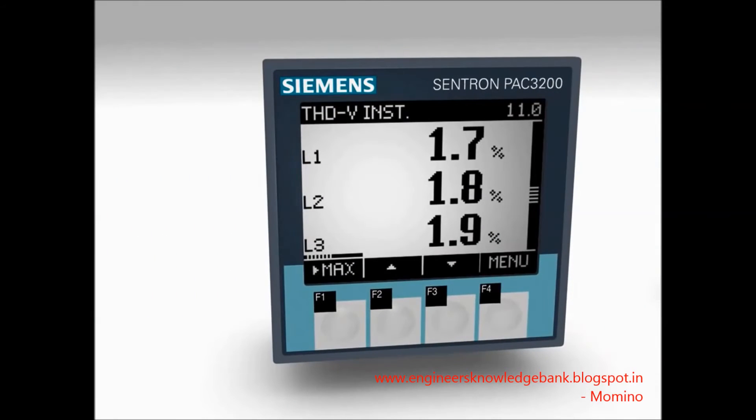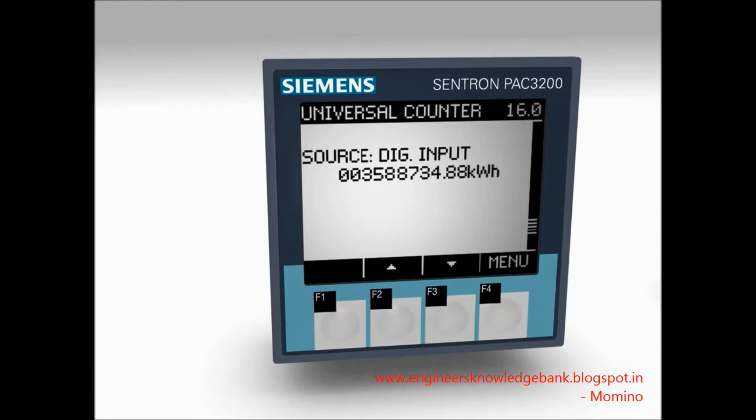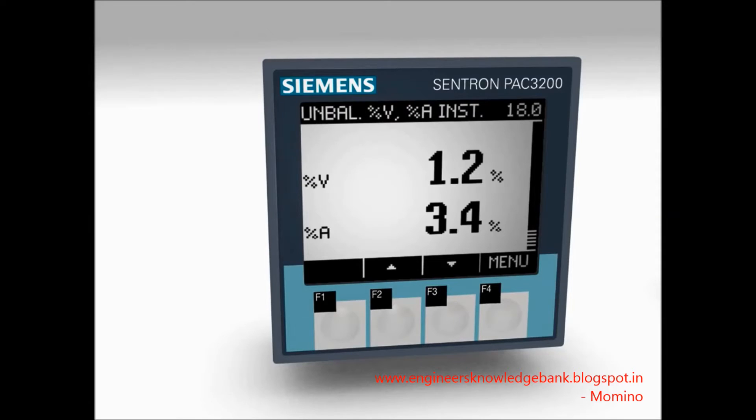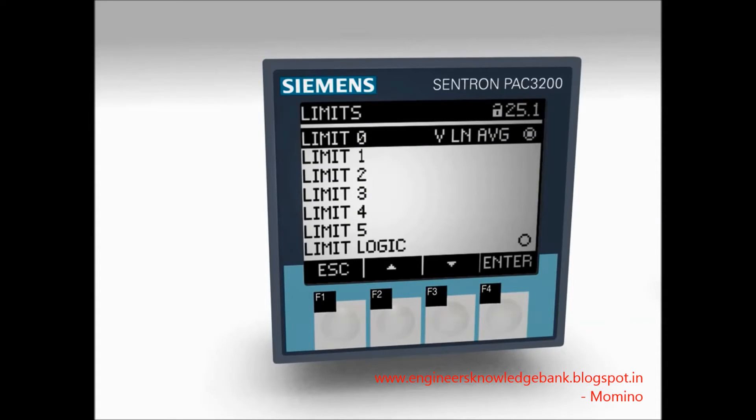The measuring device SENTRON PAC3200 provides more than 50 measurements and can be directly connected to a network up to 690 volts. Ten precise energy counters permanently log energy supply and recovery. The energy consumption of an electricity counter with pulse output can be measured via the digital input. With the limit value monitoring function with integrated logics as well as asymmetry display system, failures can be detected at an early stage and prevented.